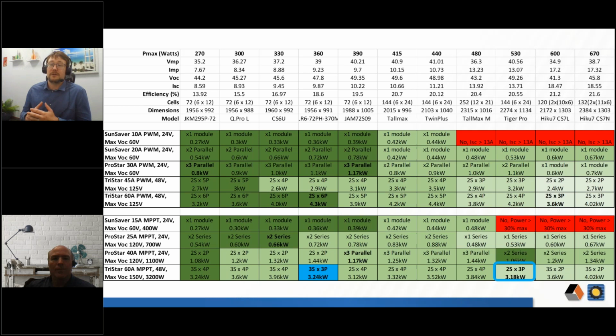What I want to emphasize about bifacial modules from our standpoint that makes it tricky is sort of 2 or 3 things. One, when it comes to sizing the charge controller, you need to use the maximum output assumption of the bifacial modules, which in my experience is always pretty much listed as 30%. So they'll give you an electrical specifications table for the base monofacial output and then bifacial output at 5, 10, 15, 20, 30%. You've got to use that max 30% so that you're being conservative in your electrical design. And that's going to carry all the way through to your balance of systems and circuit protection. So all your circuit breakers, all your wire, everything needs to be sized around the assumption of that bifacial output.